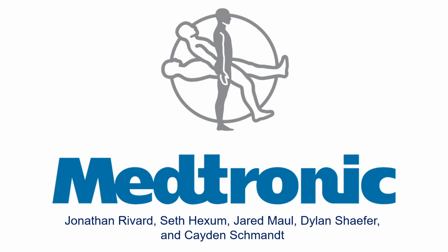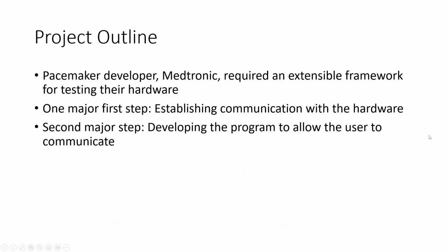What Medtronic has tasked us with developing is a sort of testing harness that allows us to craft commands that will be sent to the patient connector, which is then sent to the pacemaker device itself. This is both to test general functionality of both devices, and it acts as a form of security testing, as it allows a user to send malformed commands both to the patient connector and pacemaker to ensure they don't behave in any unforeseen ways. The first major step in this would be establishing serial communication with the hardware itself, and then developing a program that allows the user to communicate with these devices.